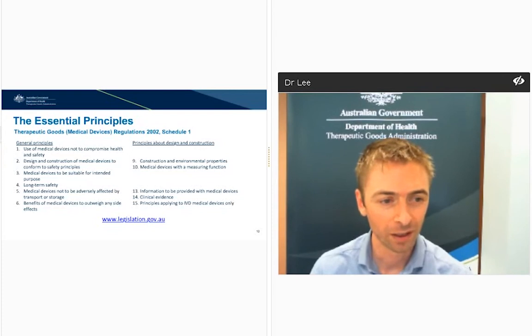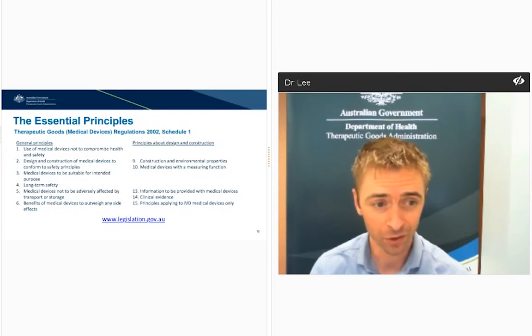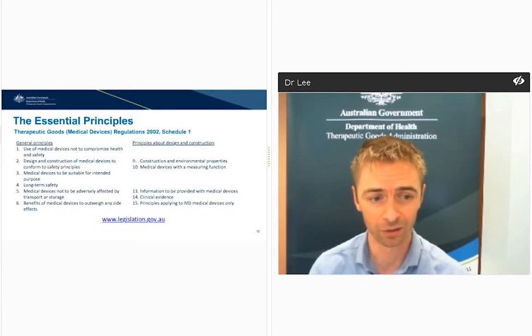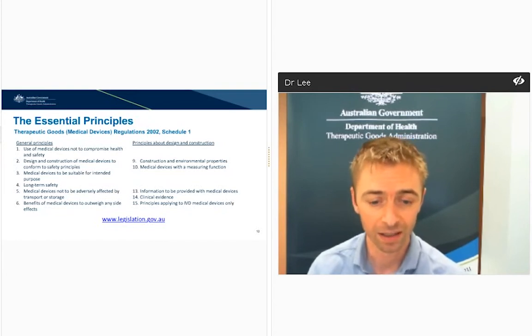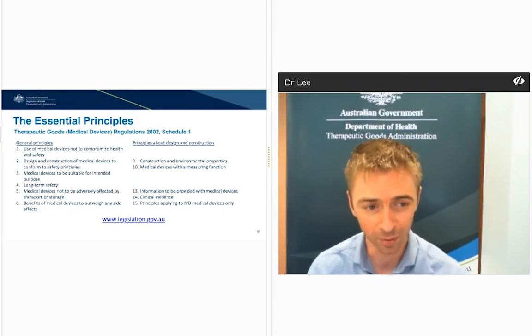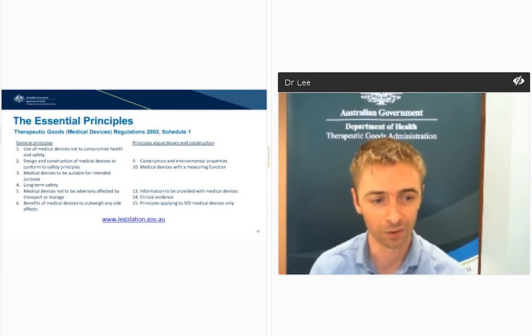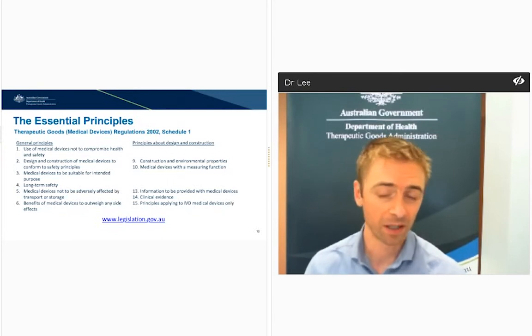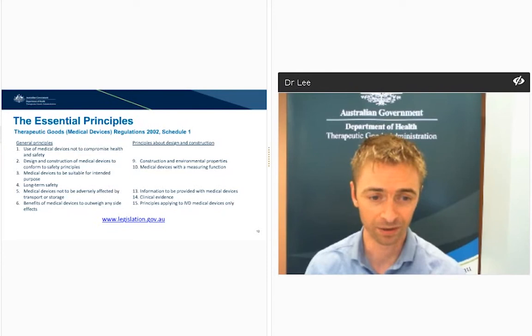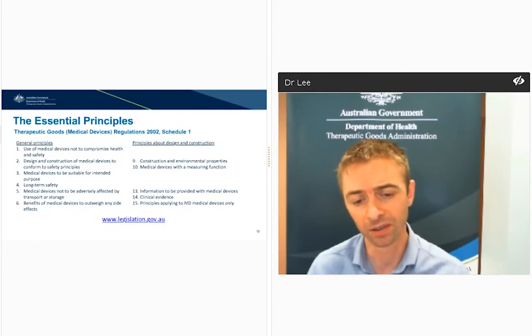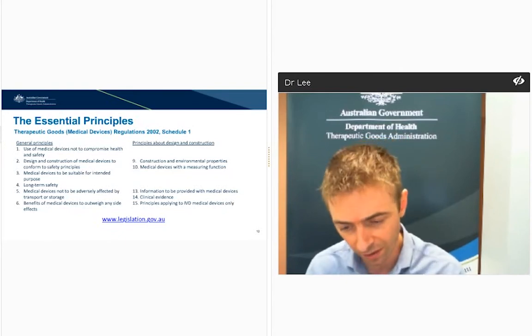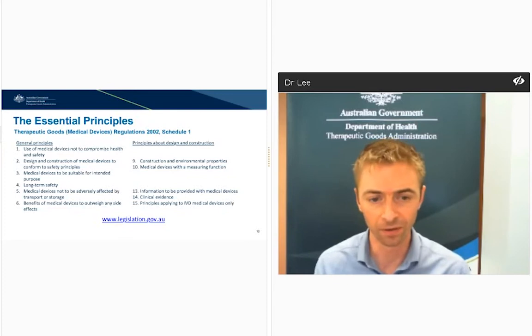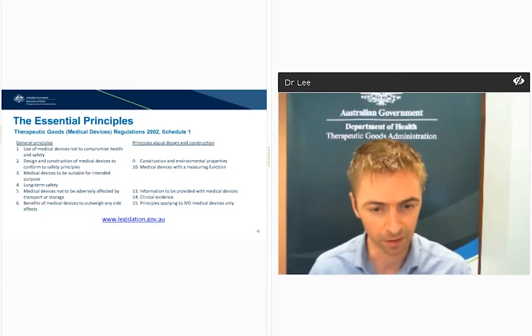So when you're developing your device, regardless of software or hardware, you need to be able to demonstrate that it won't compromise health and safety. You need to be able to demonstrate that you've designed and constructed it safely, that it's actually appropriate for the intended purpose you've given it, that it's going to be safe in the long term. Okay, you need to provide information with your device regardless of what it is. So particularly if you're new to regulation and you're making software devices, don't make the mistake of trying to narrow in on just the software principles. Okay, you need to look at the whole lot and actually go through and say, what do I need to do under each of the 15 EPs in order to demonstrate compliance?